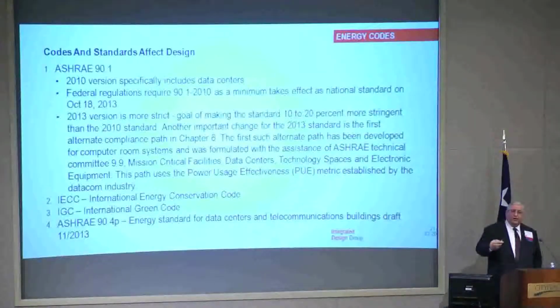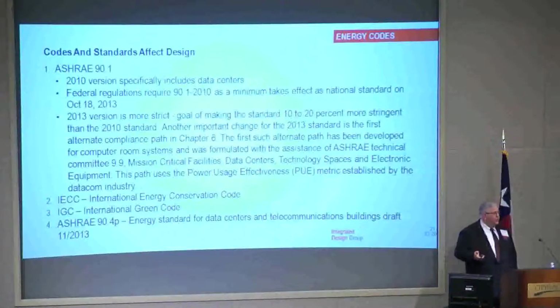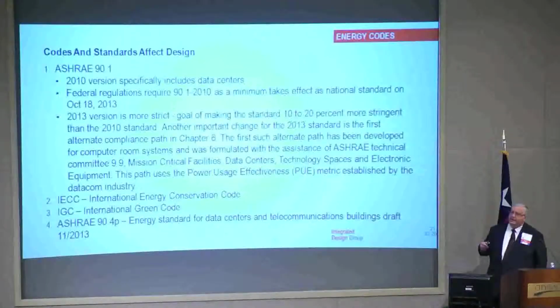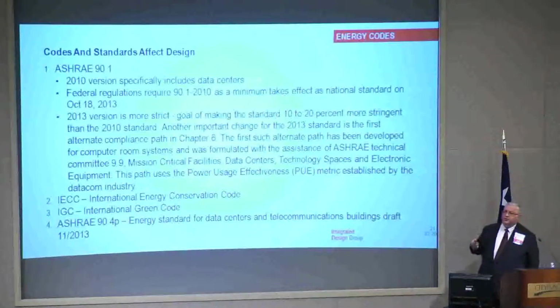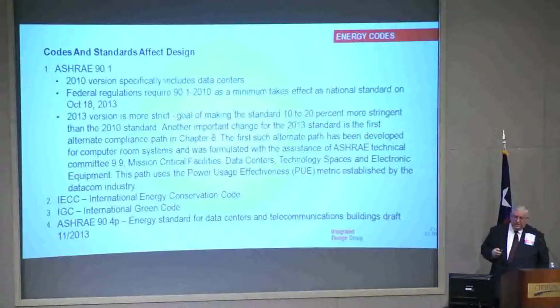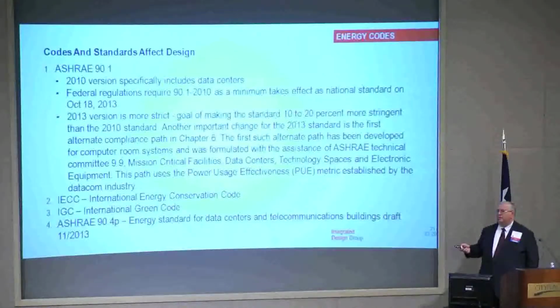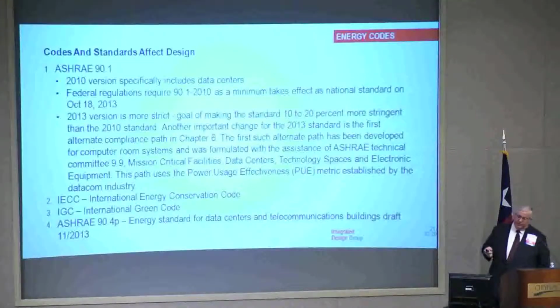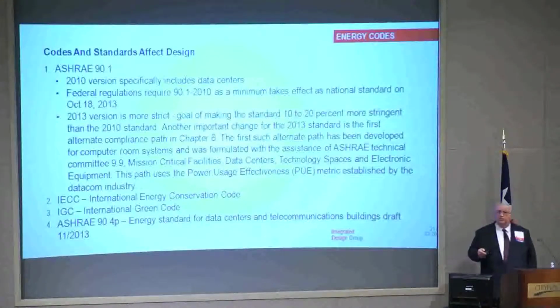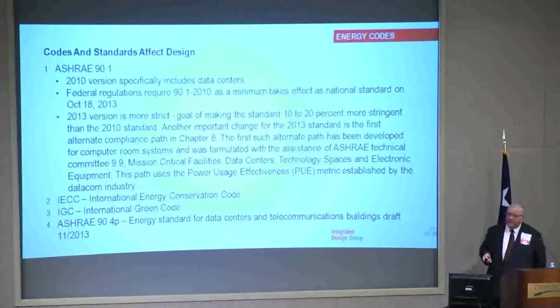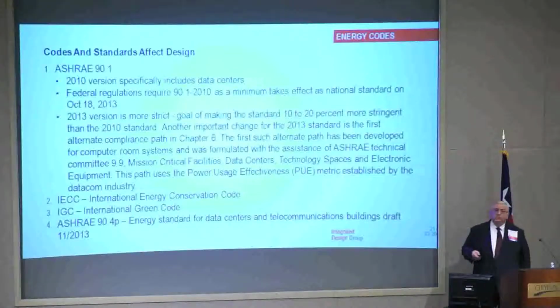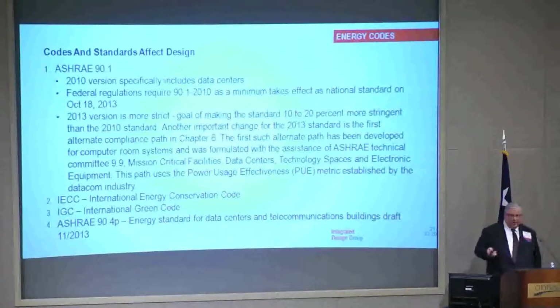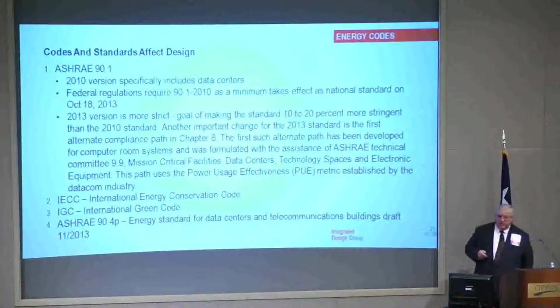Codes and standards affect our designs, which is why it's important to know what standards we are trying to follow. The 2010 version of 90.1 is an energy code requirement specifically called into data centers. It came out in 2010 and is just now becoming a requirement in many states. Federally, it was required as of last October to be the minimum code requirement in all states. Last year, they issued the 2013 version, which will take a couple more years before states start adopting it, and that's even another 10 or 20% more energy efficient than the previous standard.